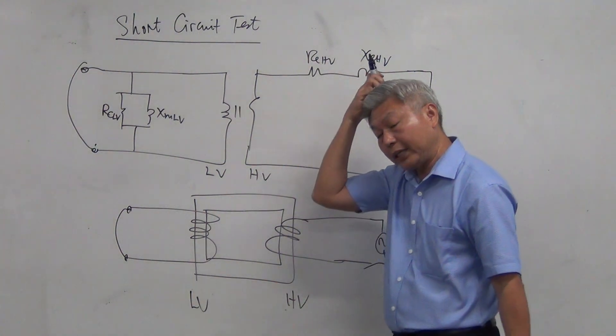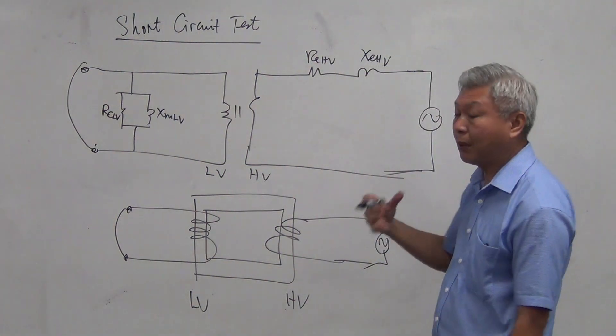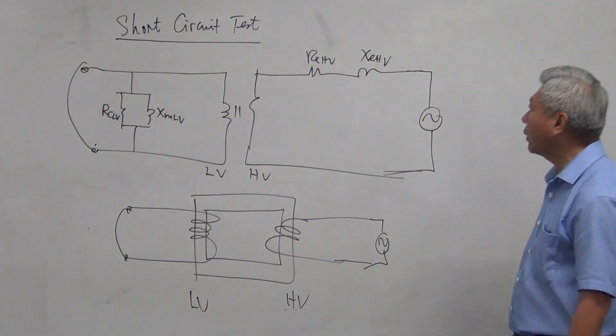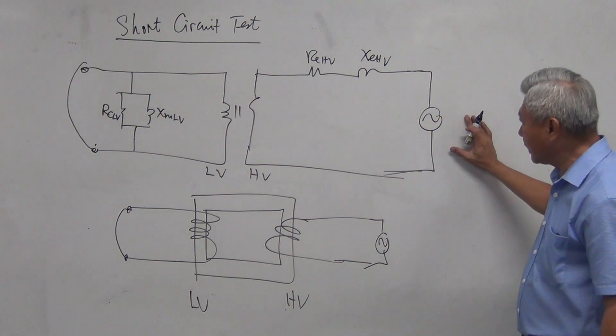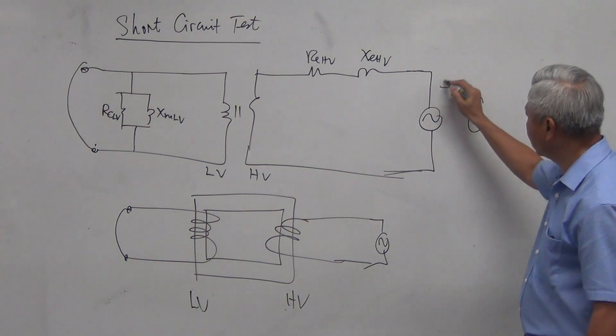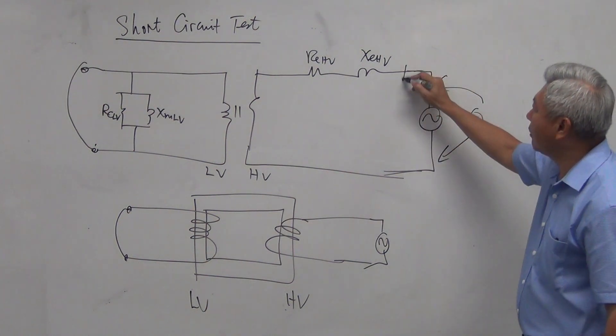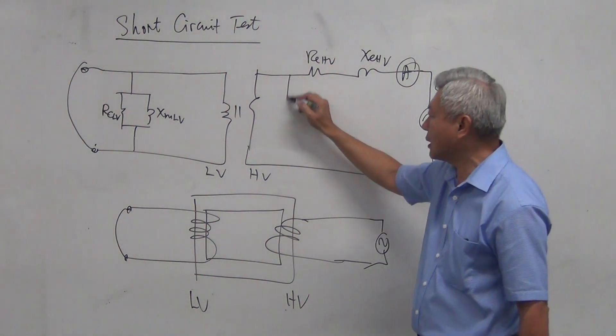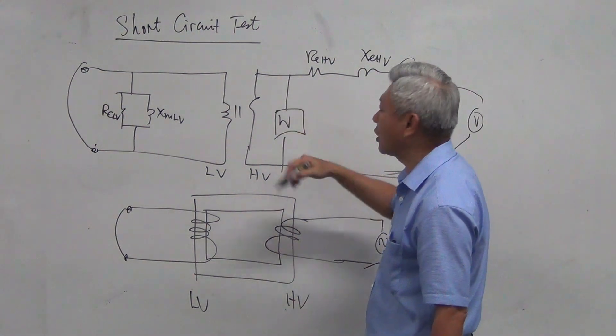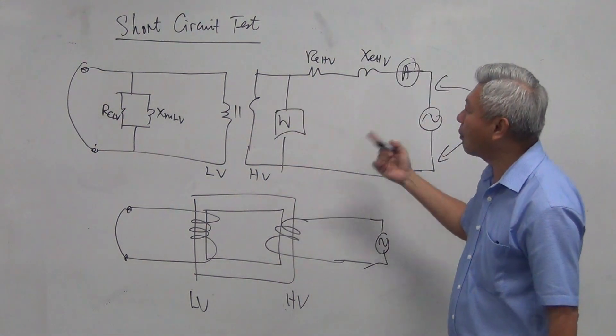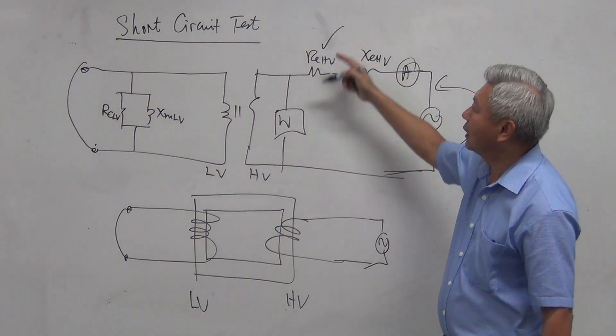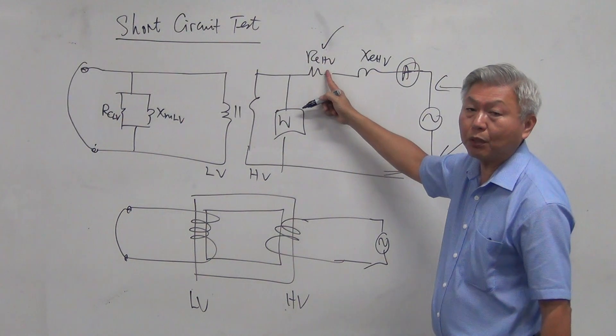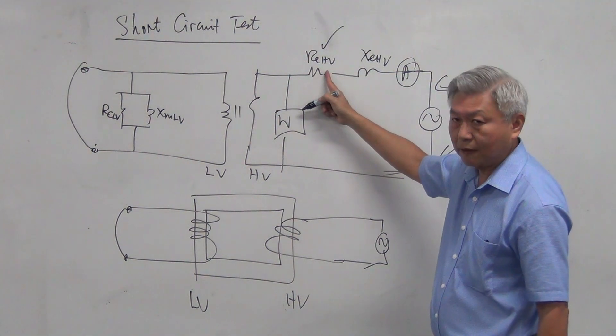Short circuit is quite dangerous, so therefore we perform the experiment at a very small voltage instead of a high voltage. We put a voltmeter here to measure the voltage, an ammeter here to measure the current, and a wattmeter here to measure the power. The power measured will be the power that occurs in REHV, because real power is what happens in the resistive part of this circuit.